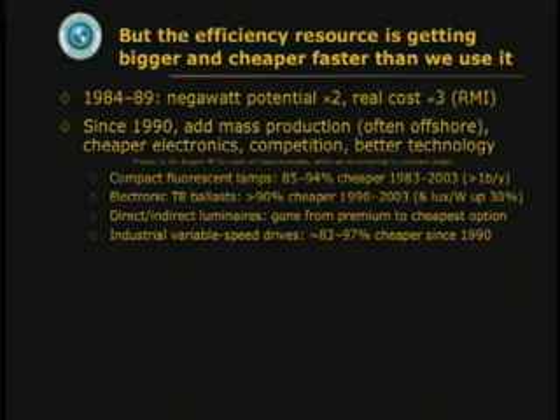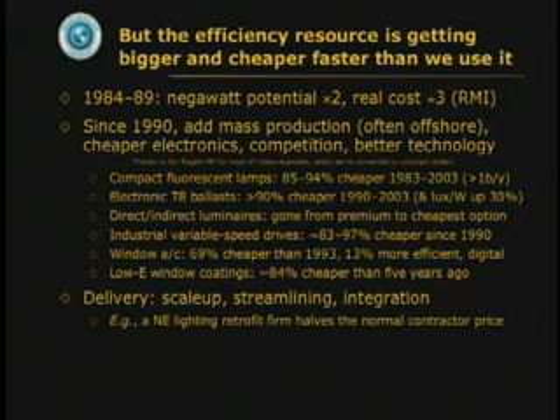Industrial variable speed drives are down in cost 83 to 97% since 1990. In fact, in many parts of the country in a competitive market, the motor dealer gives you the drive for free because it's actually cheaper than putting in protective and soft start equipment they would otherwise need that's built into the drive. Window air conditioners are 69% cheaper in real terms than 1993, 13% more efficient. Low-E window coatings are 84% cheaper than just 5 years ago. Even the delivery of these technologies, that cost has dropped by about half in one competitive market I looked at just through experience and volume.